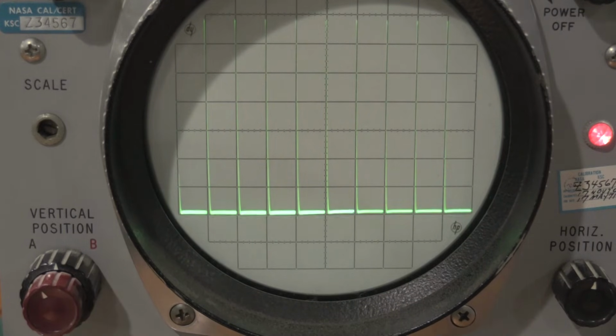Okay, so the spec on this particular scope is a 5% time base. So some of the ranges are out, but some of the ranges are still very serviceable. And anything that would be 2.5% fast, 2.5% slow, well within spec for this particular scope. So no problems there. Well, a couple of the ranges are bad and need tweaked.